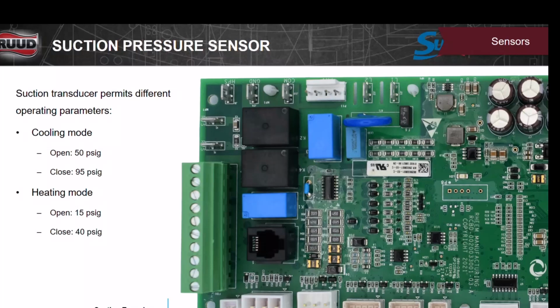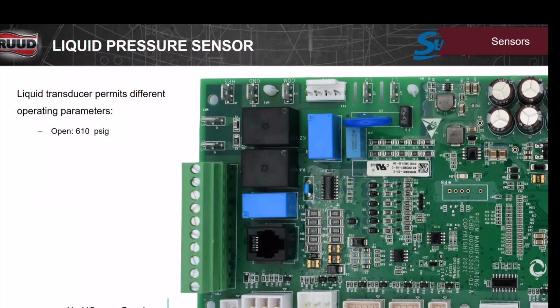This helps tell the board what the system's doing. There's two different transducers there. There's a suction and a liquid transducer. The liquid transducer permits different operating range too. Now it's going to open at 610 psi. That's your pressure switch basically. When it gets to 610, the transducer is going to say, kick it out.